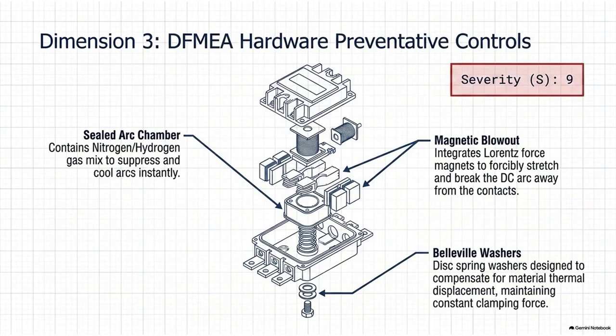The entire contact mechanism is housed within a thick, hermetically sealed ceramic or heavy composite chamber. They're essentially building a tiny, pressurized spacecraft environment just for the switch. Exactly. The internal chamber, where the high-voltage contacts live and operate, is completely evacuated of normal atmospheric air during manufacturing. It is then pumped full of pure nitrogen gas, or, in some highly specialized designs, a precisely calibrated mixture of nitrogen and hydrogen. Why specifically choose nitrogen?